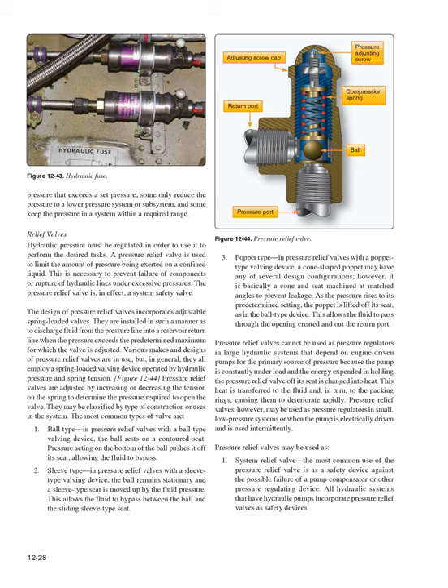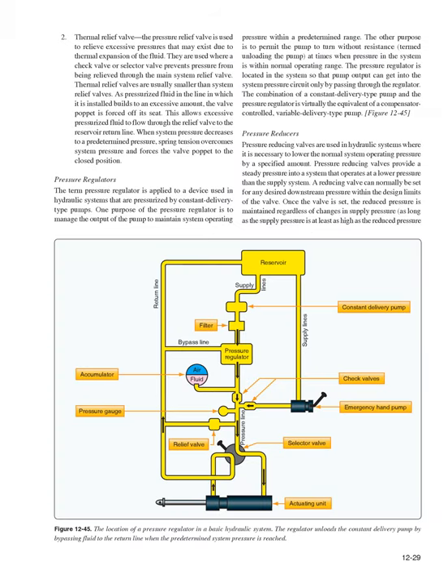Pressure relief valves may be used as, 1. System relief valve. The most common use of the pressure relief valve is as a safety device against the possible failure of a pump compensator or other pressure regulating device. All hydraulic systems that have hydraulic pumps incorporate pressure relief valves as safety devices. 2. Thermal relief valve. The pressure relief valve is used to relieve excessive pressures that may exist due to thermal expansion of the fluid.